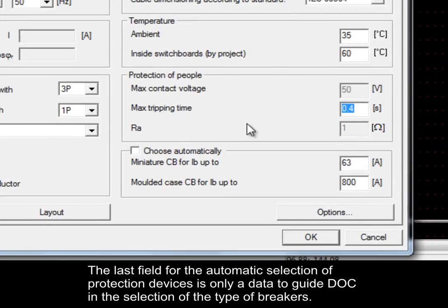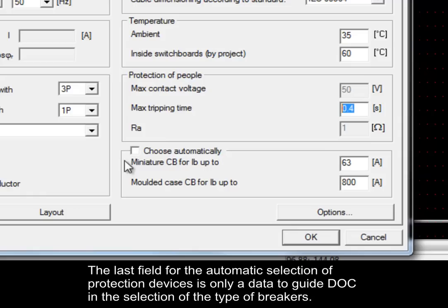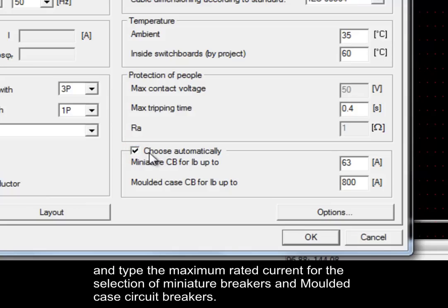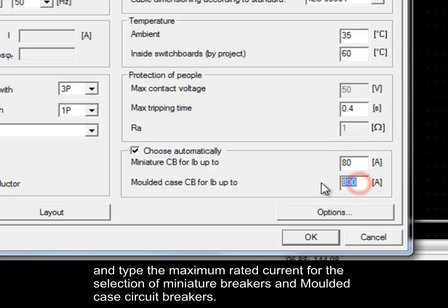The last field for automatic selection of protection devices is only a data to guide DOC in the selection of the type of breakers. Insert the tick in the checkbox to enable it and type the maximum rated current for the selection of miniature circuit breakers and molded case circuit breakers.